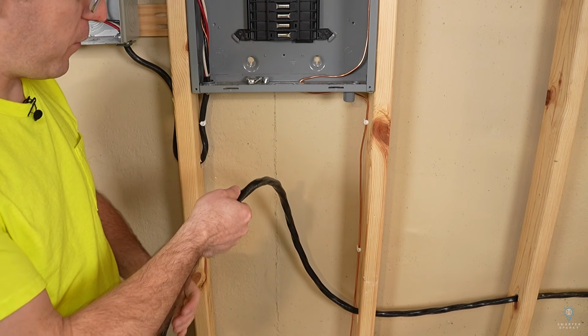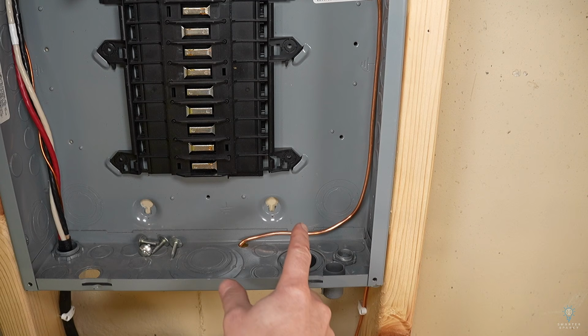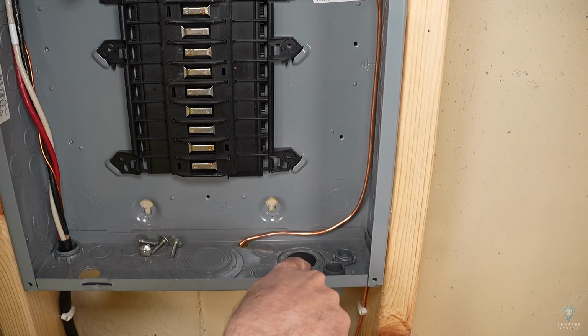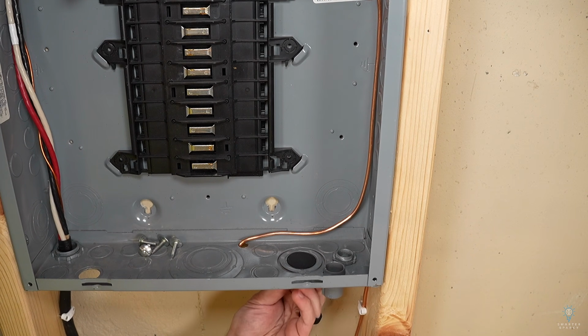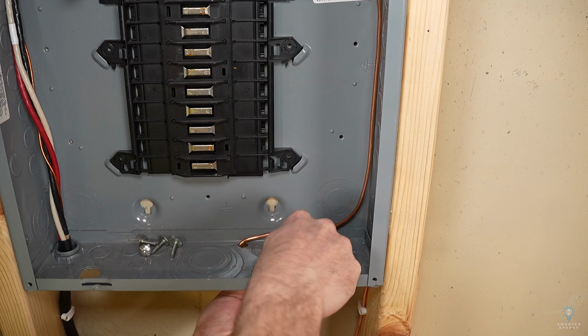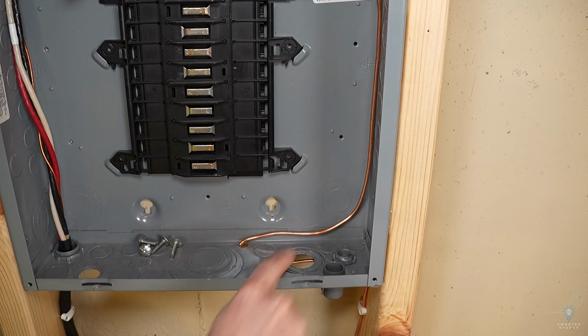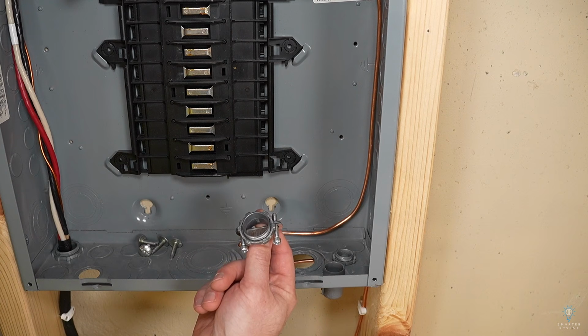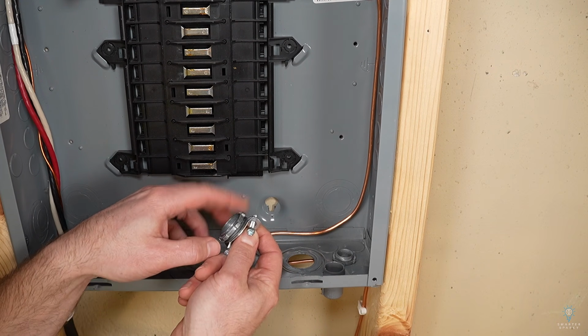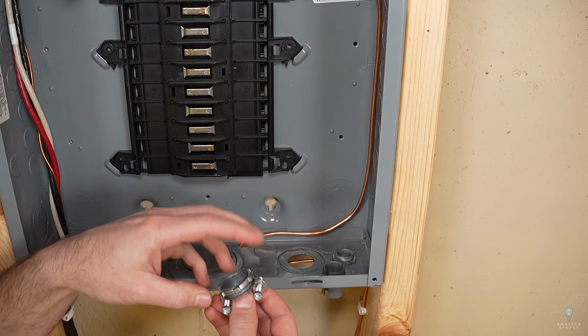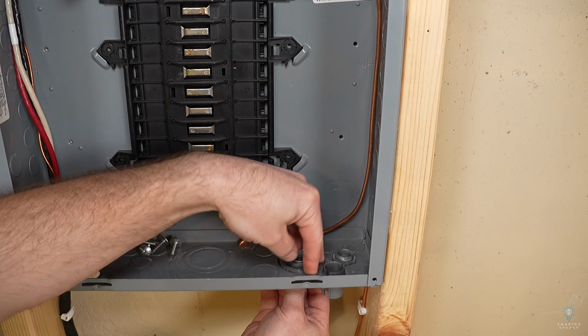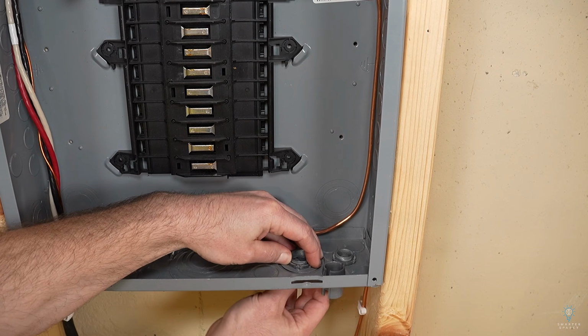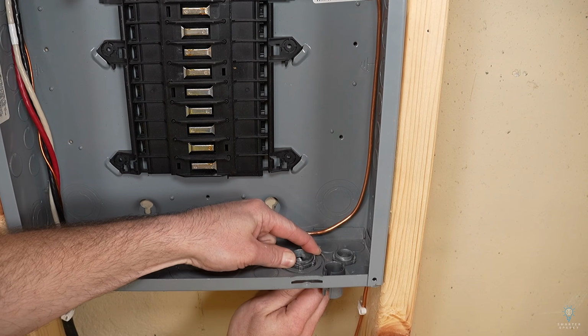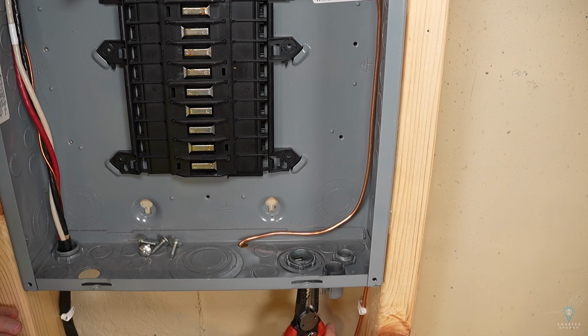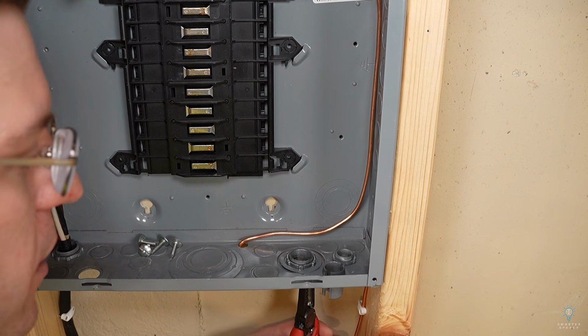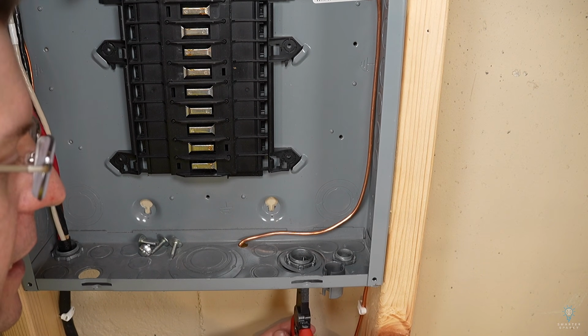So now we're going to get our feeder up into this electrical panel. Because my main electrical panel is used, I've already got some knockouts that are out of this, so I'm just gonna reuse one of these knockouts that are already here. This is a 3/4 inch knockout, which is exactly what we need for our 3/4 inch cable connector. So just like with the sub panel, we take that lock nut off and we can install this connector like so. I'm also gonna do that trick where I turn it sideways 90 degrees and then use the pliers to bring it the other 90 degrees, and that will tighten it up.